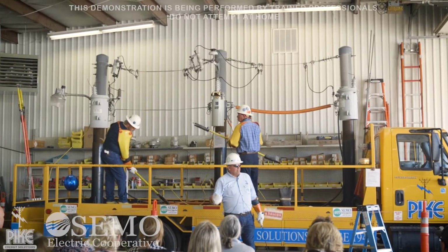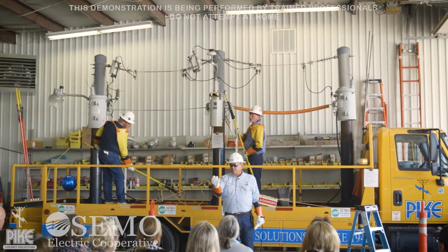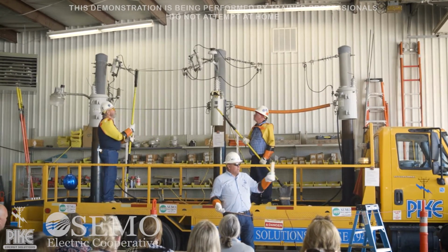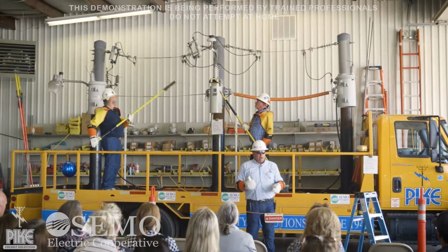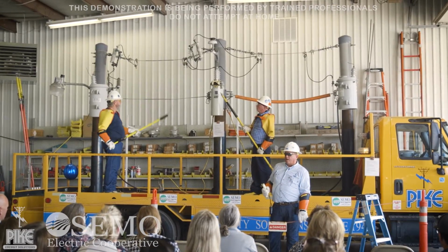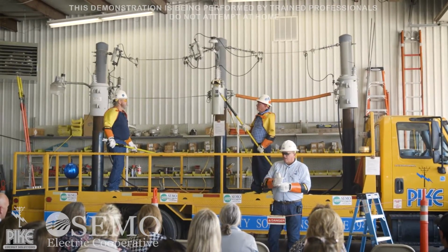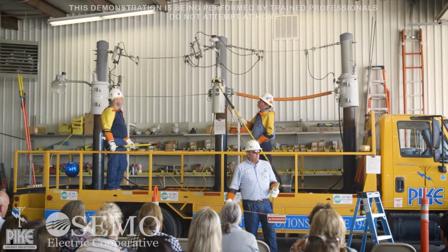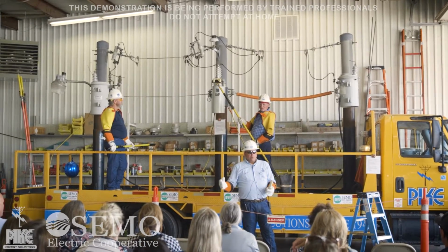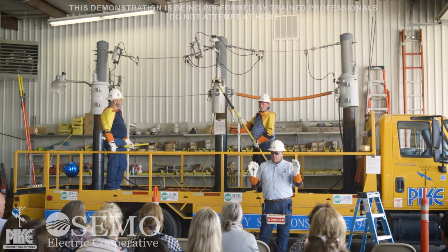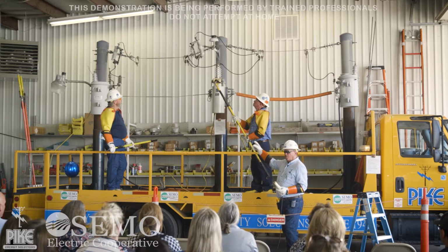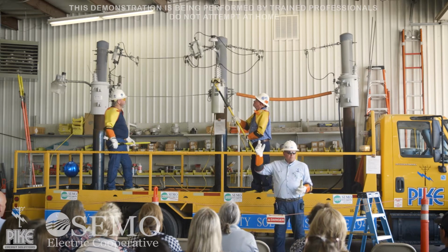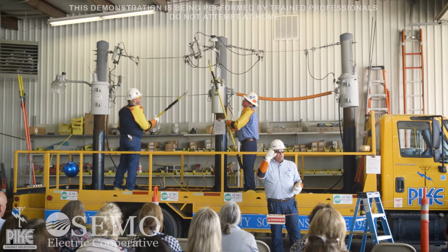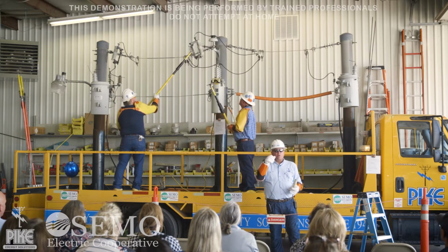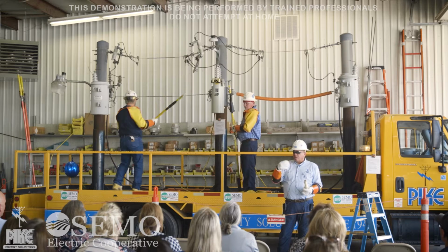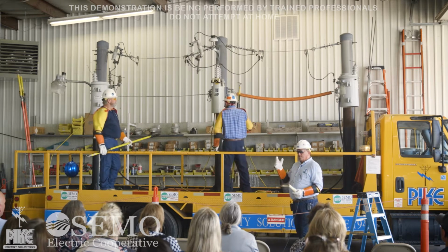As an example, let's say this barricade is a single-phase tap, fed off the main line but also fed off a fuse tap. There's a fuse behind this tap, and there's a fault that gets on this line, on this tap. What's going to happen? It's going to send a signal, so to speak, back to this recloser, indicating there's a fault on that line. The recloser is going to open up, then reclose, hoping the fault will clear up. So we're going to put it through its operation.